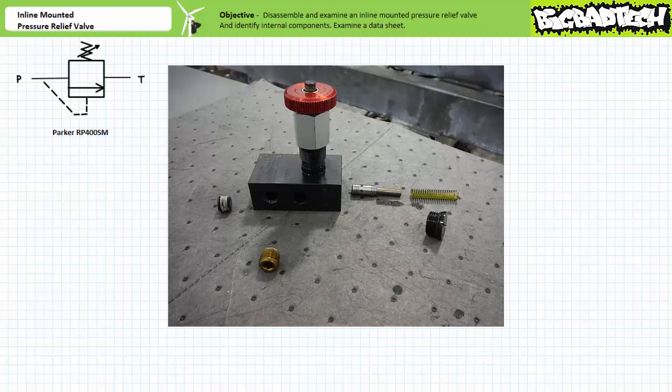Then pull out the primary piston. Note the piston isn't unusually discolored, silted over, or covered with any sticky residue or varnish. We'll examine contaminants and the means of filtering and conditioning fluid in later lectures. Note the pilot piston should travel freely in this primary passage. The primary section is essentially cleared.